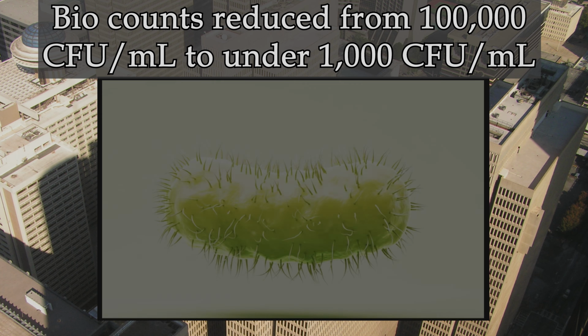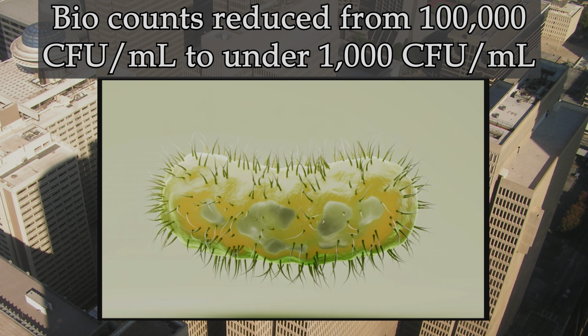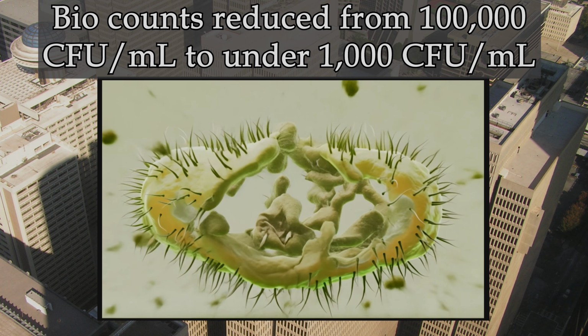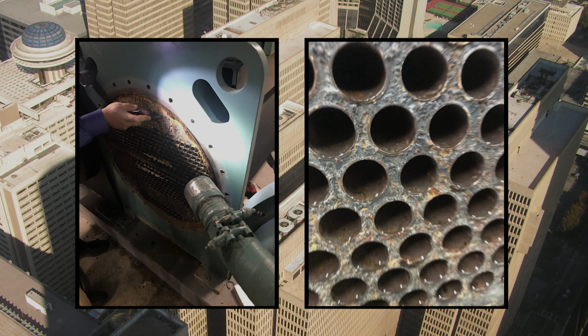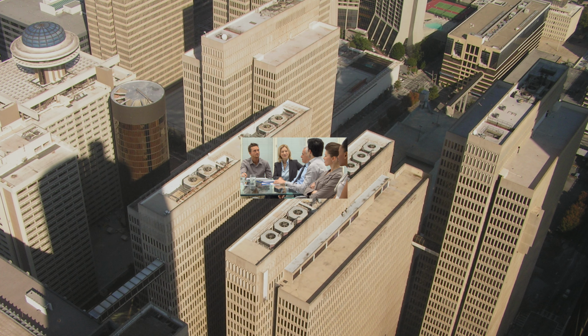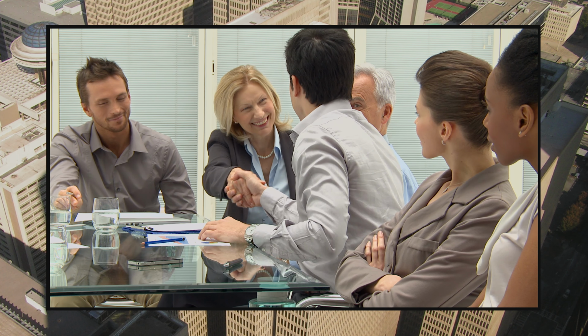Bio counts reduced from 100,000 CFU per milliliter to under 1,000 CFU within a week, while scale and biofilm accumulation in the cooling tower and chiller tubes significantly decreased. With an impressive ROI of roughly 6 months, the customer decided to install additional HydroFLOW devices throughout the complex.